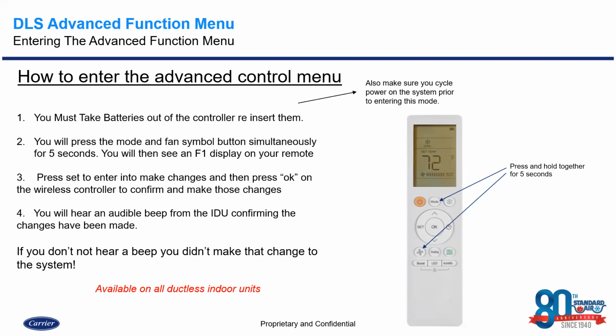When you see that 1 on your screen, you want to point that wireless controller at the indoor unit and hit the OK button. Once you hit the OK button, you'll hear an audible beep, followed by an F-1 if you change it to a 1. If you change it to a 2, it'll come up with an F-2 if you have a digital display on the high wall units. On non-high wall units, you will not see this. What you will hear is an audible beep, and that will be your confirmation that the command is sent to the unit and received. Okay, and it's important to note, if you do not hear a beep, you did not make a change to the system.